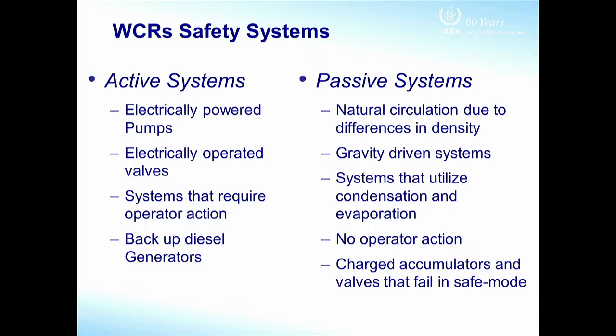It means that you have a certain period of time in which you can even abandon the reactor to itself, and you don't need any intervention of the operator, even in a very emergency case, even under accident, for a certain period. For instance, for the AP1000, they have calculated, with all the uncertainties, that the grace time is at least 72 hours. And under some circumstances, if the accumulator recharges, actually, this grace time should be infinite. But again, be careful, because this is true on the basis of the probabilistic safety analysis. Of course, there are uncertainties on that. But for sure, the adoption of passive safety systems gives the system a very important grace time in which the operators can organize themselves in order to then intervene on the reactor. This is for sure one of the main advantages of adopting the passive system.